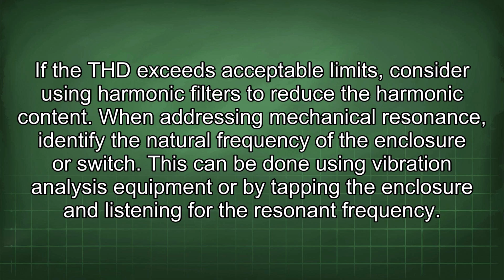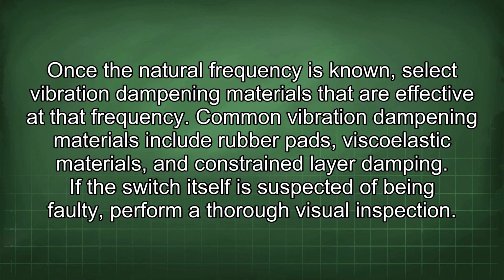When addressing mechanical resonance, identify the natural frequency of the enclosure or switch. This can be done using vibration analysis equipment or by tapping the enclosure and listening for the resonant frequency. Once the natural frequency is known, select vibration dampening materials that are effective at that frequency. Common vibration dampening materials include rubber pads, viscoelastic materials, and constrained layer damping.